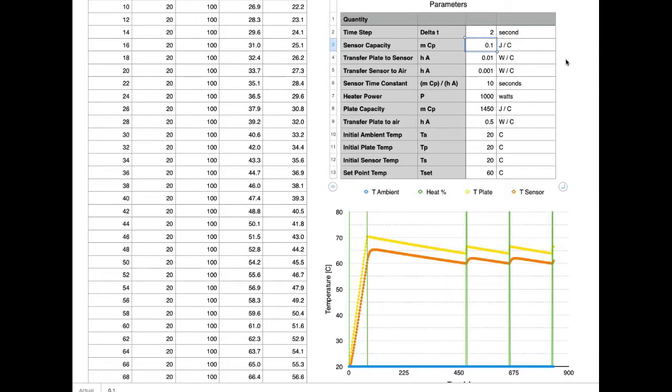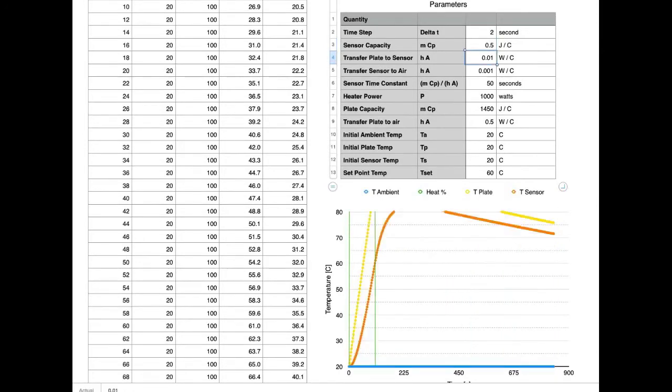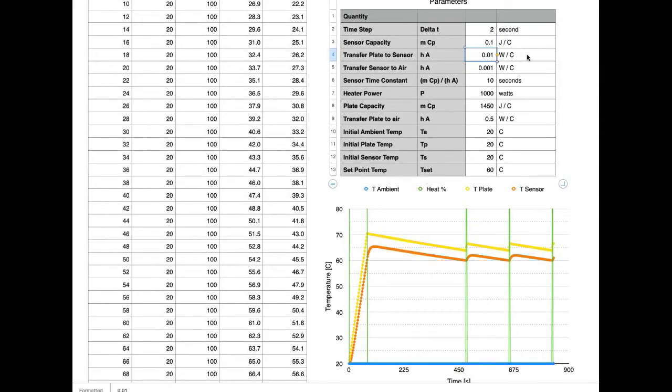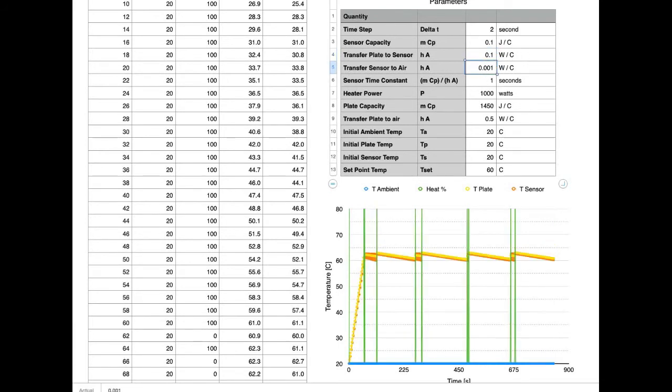So if the sensor was heavier, say 0.5 instead of 0.1, it would respond much more slowly and things go off the graph. If I switch that back to 0.1 and make the transfer from the plate to the sensor much more effective, then I see that the sensor temperature follows the plate temperature much more closely. They're much closer together.